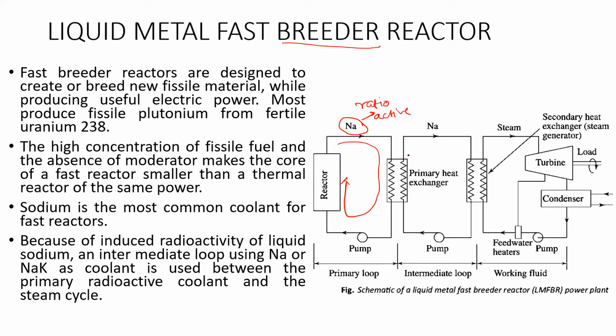So for security purposes, they have provided an extra loop of sodium, so the sodium coming out of the reactor will not come in contact with the steam or water loop. Whatever heat is associated with the sodium coming out of the reactor will be exchanged here with the other loop of sodium. Again, the heat of that sodium is exchanged in an extra heat exchanger with the water.